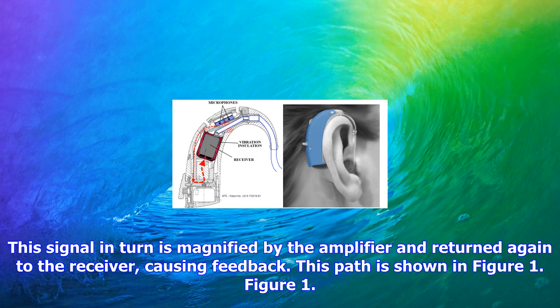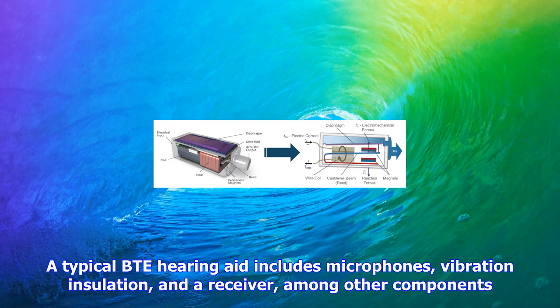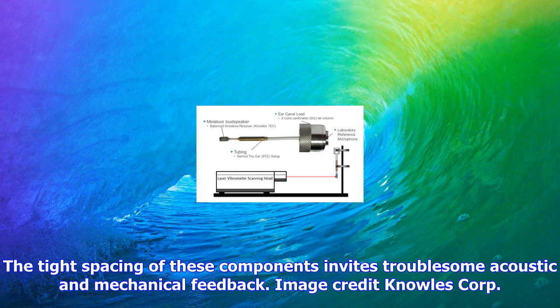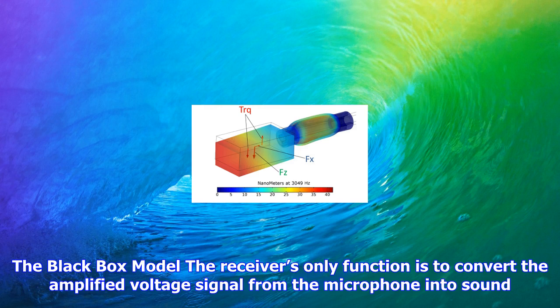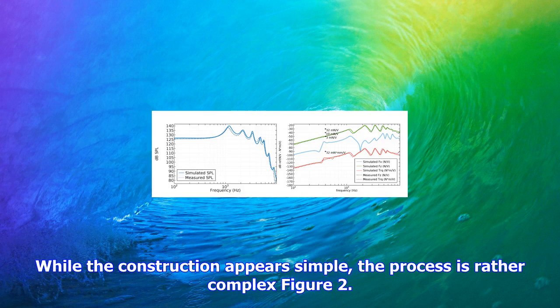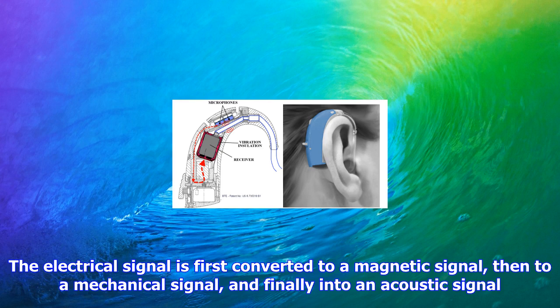The receiver contains an electromagnetically controlled lever, known as the reed, connected to a diaphragm which generates sound through its oscillating motion. The internal electromechanical forces also generate reaction forces which transmit vibrations through the hearing aid package, creating sound that is picked up by the microphone. This signal in turn is magnified by the amplifier and returned again to the receiver, causing feedback. This path is shown in Figure 1. Figure 1. A typical BTE hearing aid includes microphones, vibration insulation, and a receiver. Among other components, the tight spacing of these components invites troublesome acoustic and mechanical feedback. Image credit: Knowles Corp.